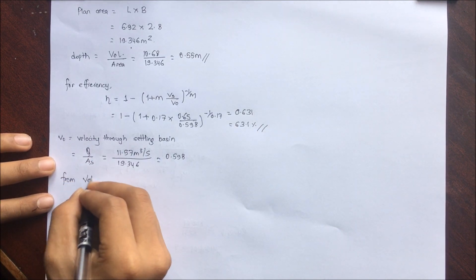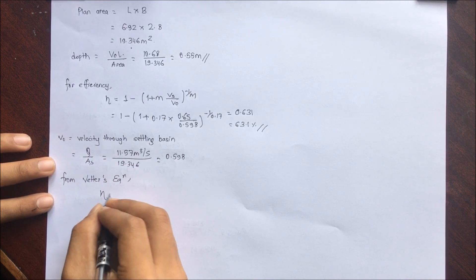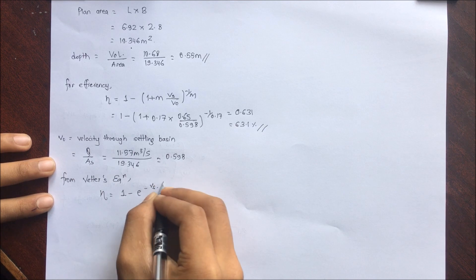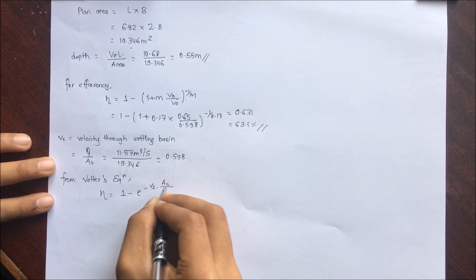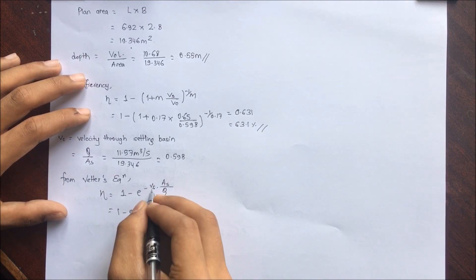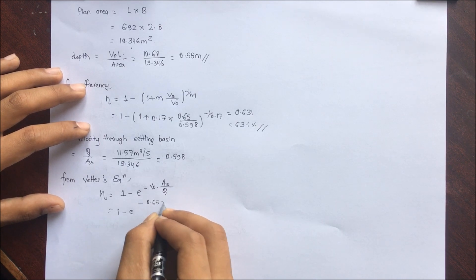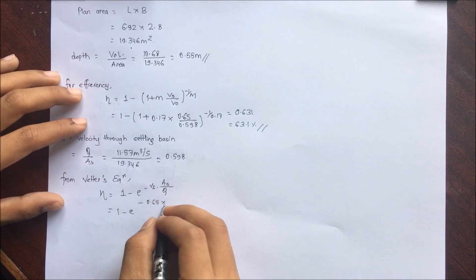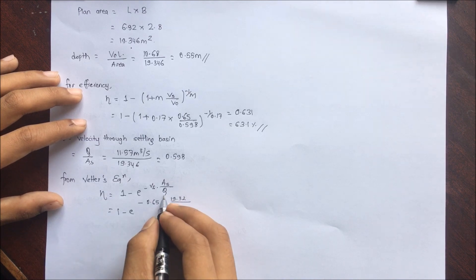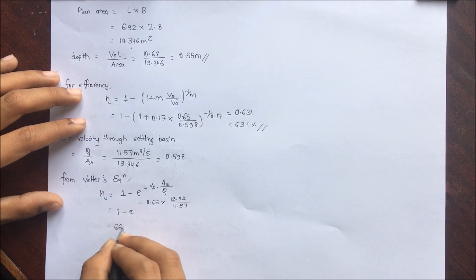From Vetter's equation: η = 1 − e^(−vs × As / Q) = 1 − e^(−0.65 × 19.346 / 11.87) = 66.32%.